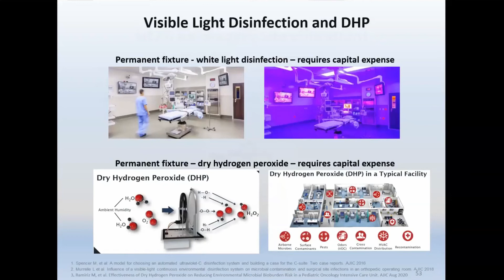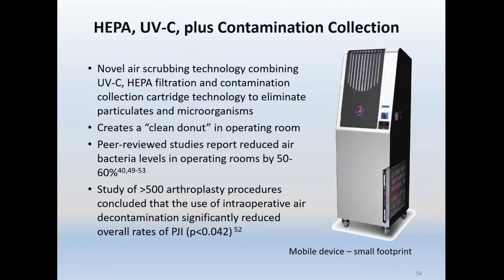This is the novel air scrubbing technology I mentioned, combining UVC and HEPA filtration to constantly scrub the air while it's on, working in an operating room to create that clean donut. Peer-reviewed studies report reduced airborne bacterial levels in the operating room by about 50 to 60%. A study of more than 500 arthroplasty procedures concluded that this intraoperative air decontamination system produced a statistically significant overall reduction in prosthetic joint infections.